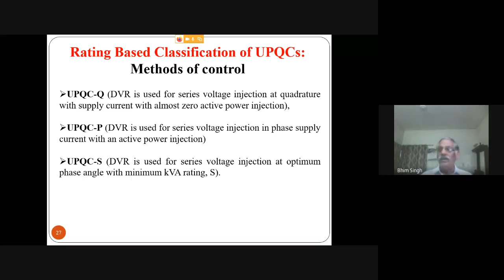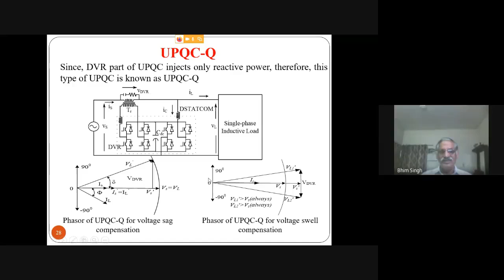Well, this is the UPQC-Q. If you have a sag, you can compensate, but a swell cannot be compensated by UPQC-Q. That is the limitation of the UPQC-Q mode of operation. Sag can be compensated, but not the swell. You cannot reduce the voltage, you can only increase the voltage by injecting. So that clearly explains the one limitation of the UPQC-Q.